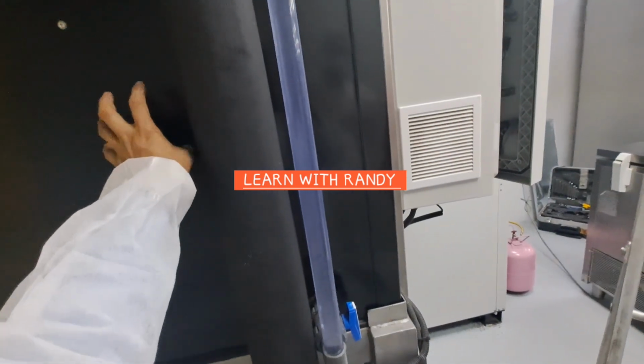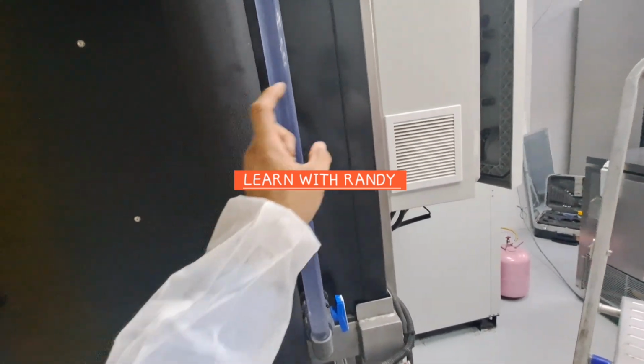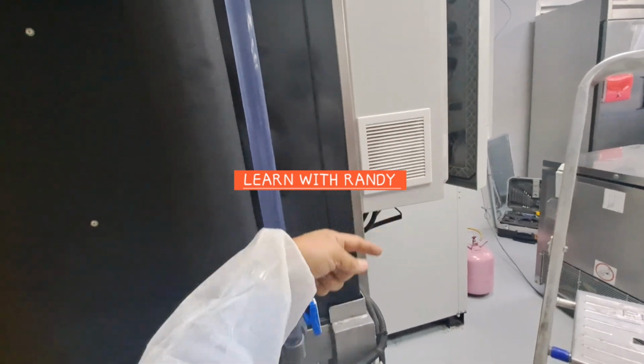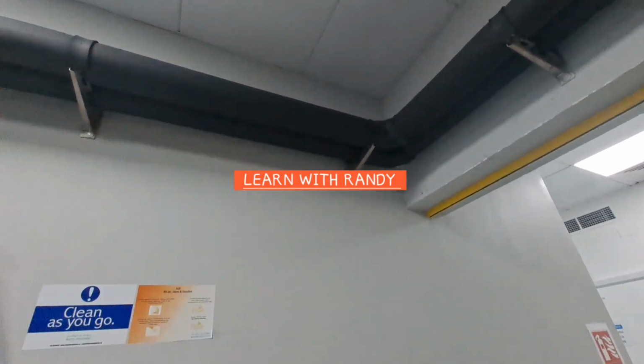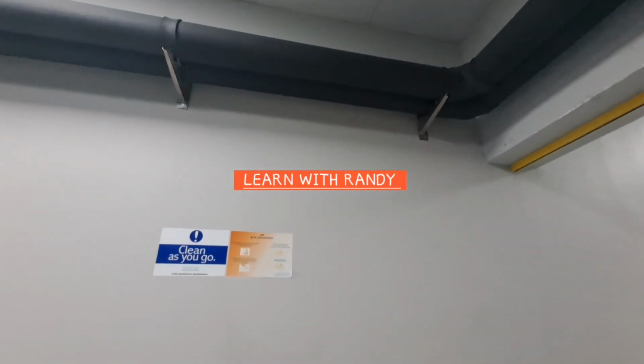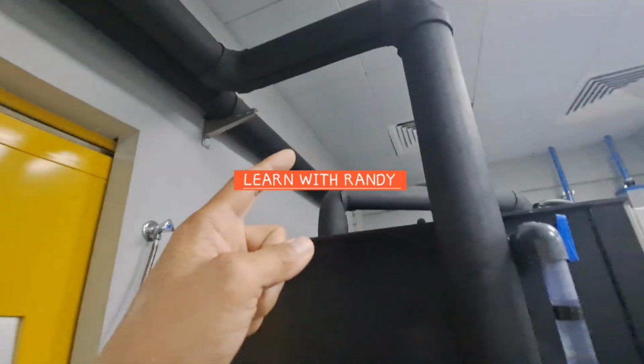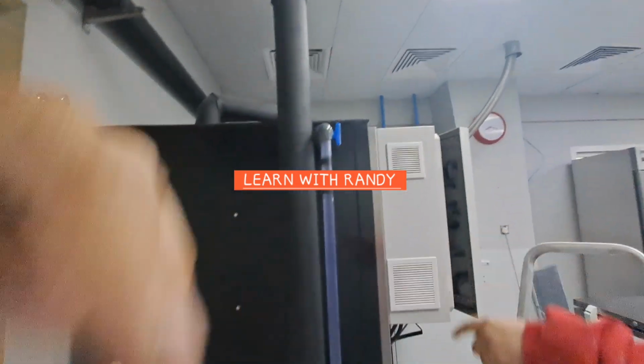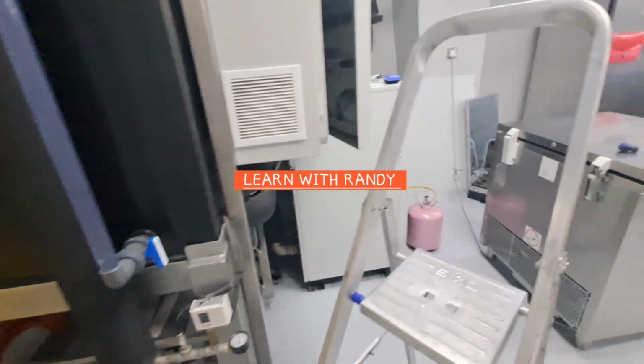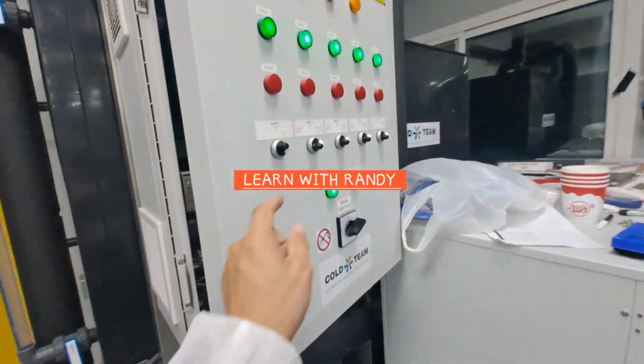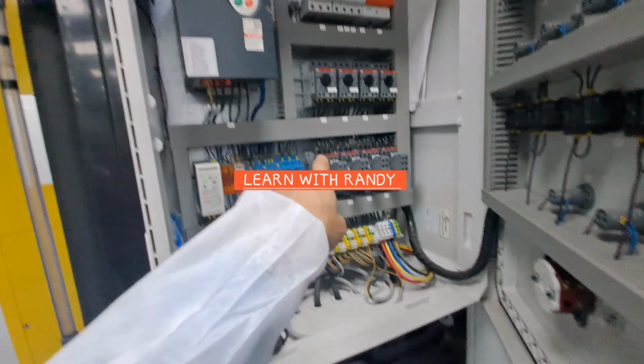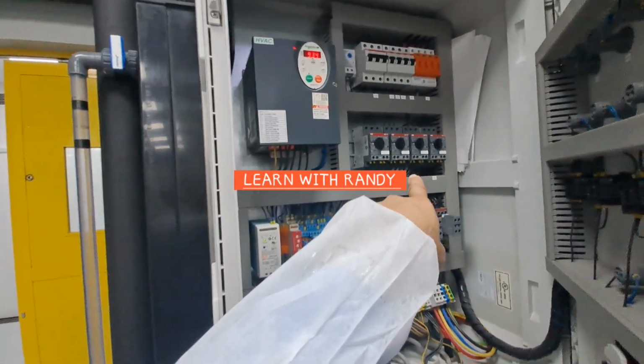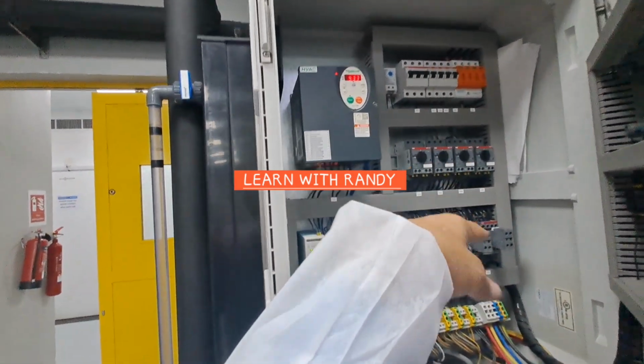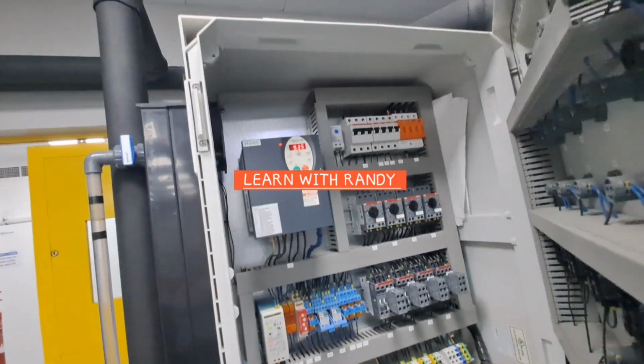From the normal room temperature water, it will go to the heat exchanger, and from the heat exchanger it will be pumped up to the inlet, and then when it goes to the tank it will cool, and then the water will return back to the tank. So the same, it circulates. Okay, so this is the controller. If I control pump one, the contactor Q20 will turn on, and then Q30 for pump 2, Q40 for pump 3, and so on. And this is the controller for the pump.